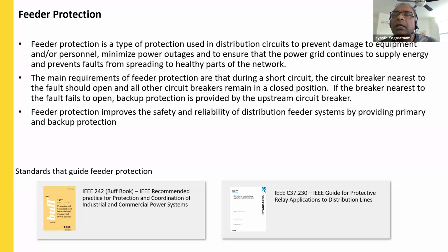The feeder protection improves the safety and the reliability of the distribution feeding system by providing primary and backup protection. So I have mentioned two standards which you might be able to use as a reference when you are thinking about feeder protections. The IEEE 242 Buff Book is one of the references we could use for the coordination of industrial and commercial power system applications, and the IEEE C37.230 provides the protective relay application guide for distribution lines.